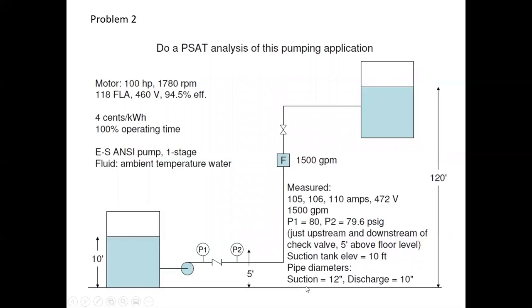Okay, so number 2, whole nother scenario. Do a PSAT analysis of this pumping application. So we got a suction tank. This time we're pumping to a discharge tank up on the hill. We got elevations. So the free surface in the suction tank is 10 feet, and going up the hill, this free surface is 120 feet. So the difference in free surfaces is what, 110 feet. And we don't have any gas overpressure, so your static head on this is going to be 110 feet.